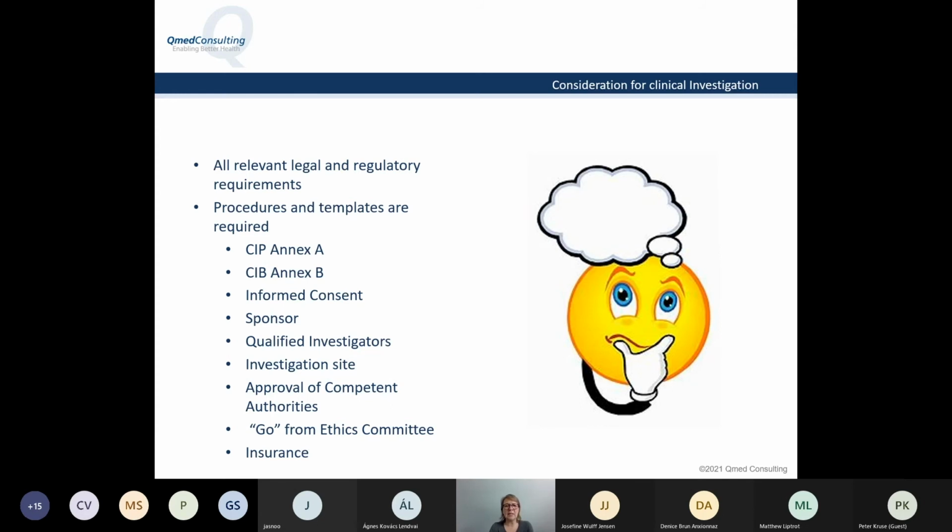We call that an investigator-initiated study. If it's a pre-CE mark device from you as a manufacturer, they would still need to submit to the competent authority, including an investigator's brochure. Otherwise, there is a risk that these data will not later be approved for CE marking because they were collected without the proper approvals. So that is just important to keep in mind.